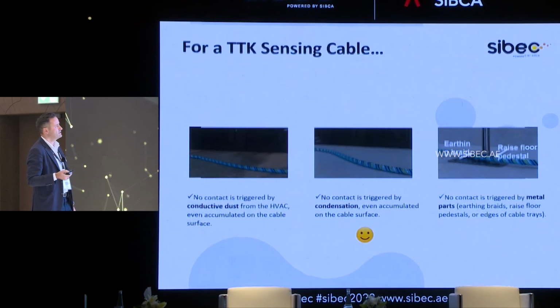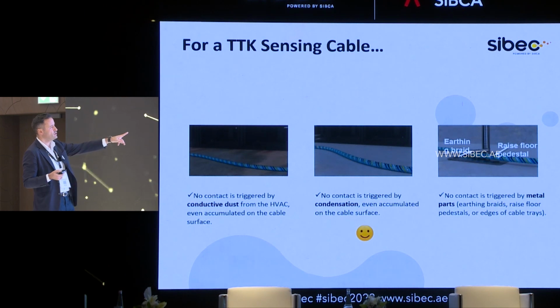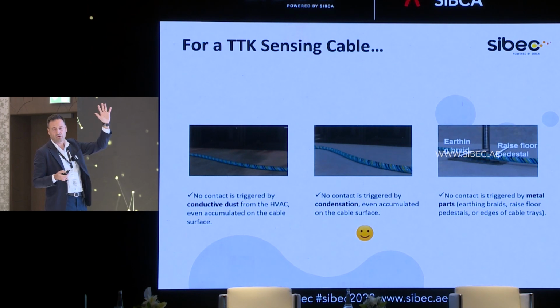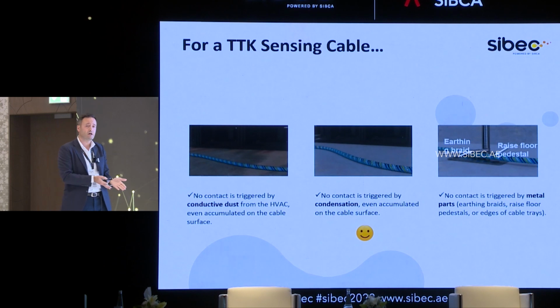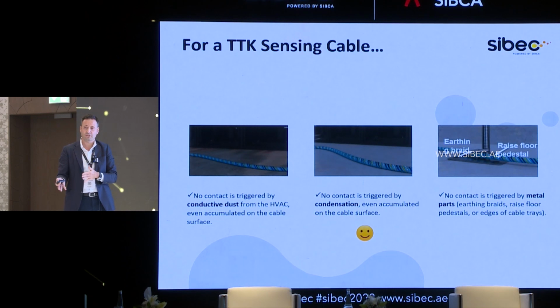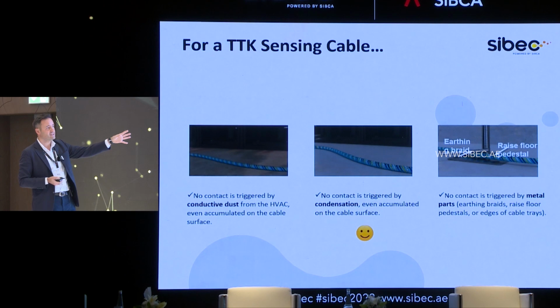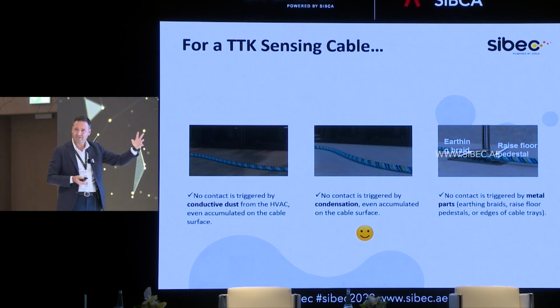Bon, this is what we discussed before. This is the sense cable itself, raised floor, under raised floor, directly exposed. We're equipping also high-level environment. I mentioned the chilled water pipe. At the moment, hyperscale data center, and that's why we do a lot of seminars with consultants. So you will see now in the consultant specification that leak detection is also part of a project requirement. So for the data center here, we will have a leak detection mentioned in large scale.